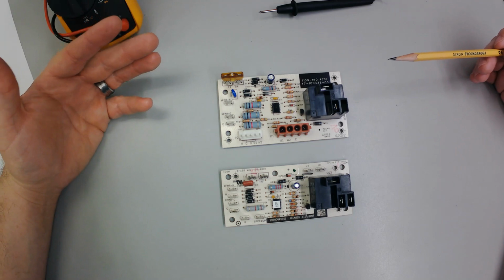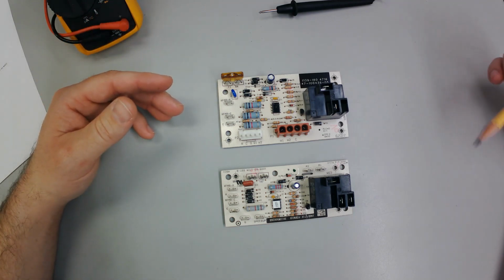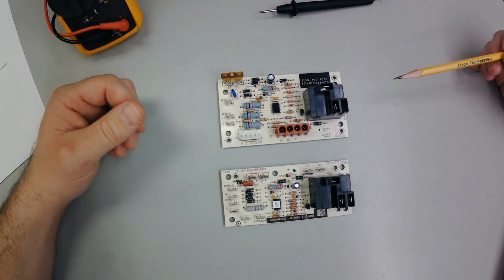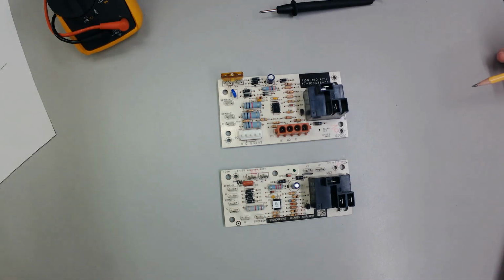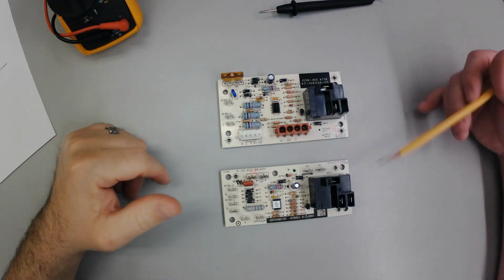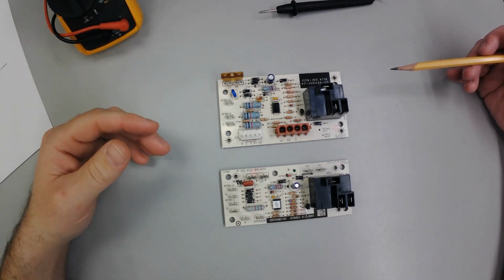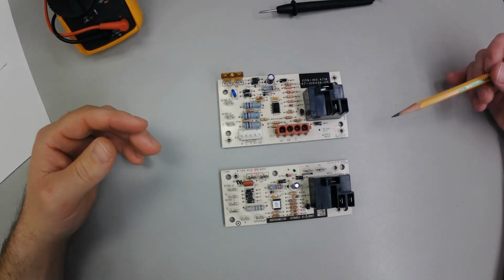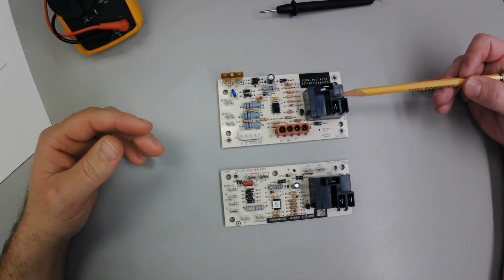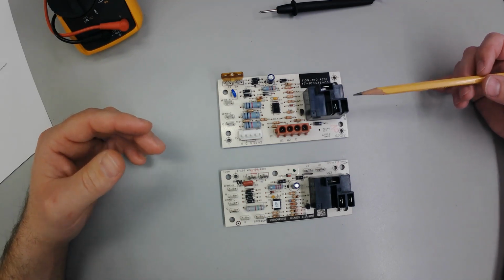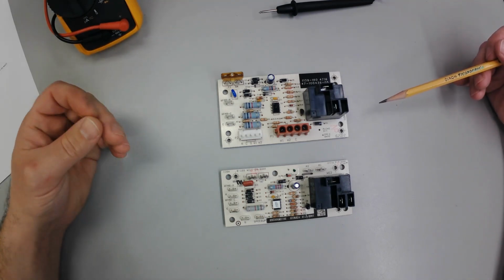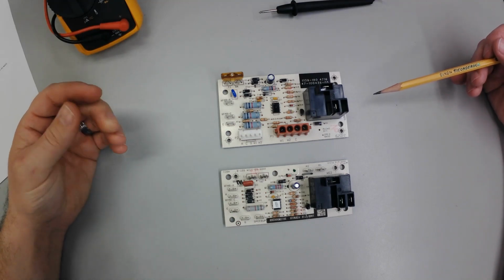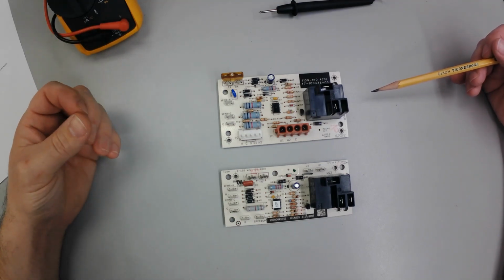And that's going to be typical of service work in the field. You have to take a few minutes and look at the diagram, look at the unit, the wiring, and figure out what's going on. So I'm just going to address a few things, try to clean it up a little bit and make it worthwhile. But this Rheem board is really not that hard. Okay, you'll typically see these with a PSC motor. So you're going to have a 3-speed PSC motor or a 2-speed.